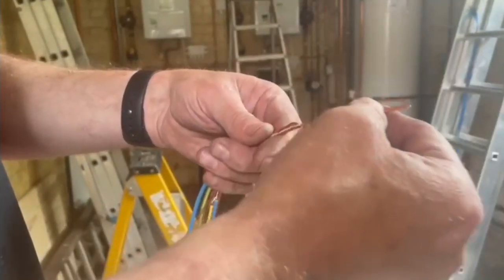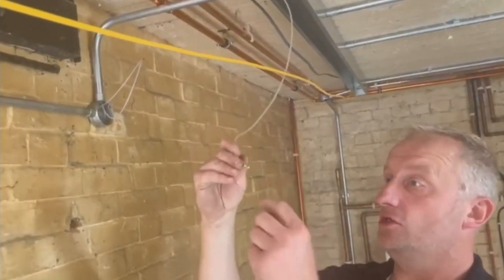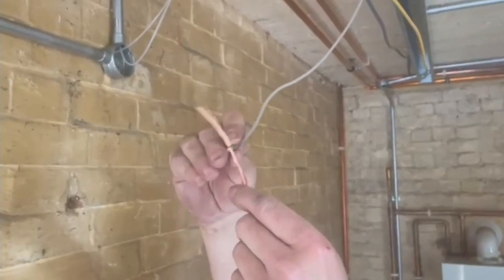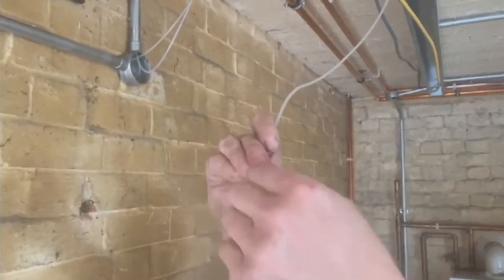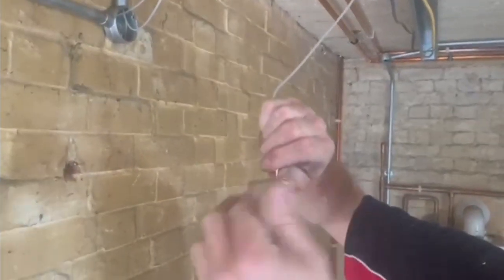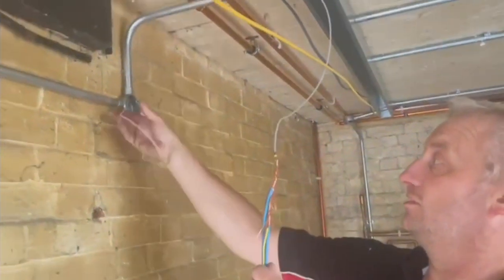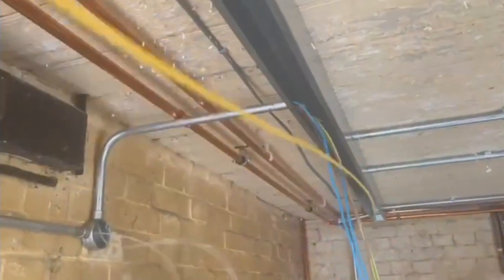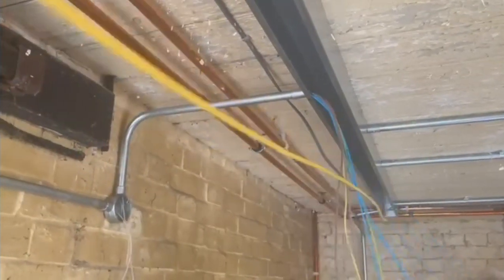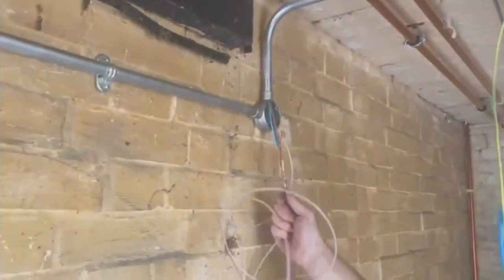So now we're going to take this bit and loop it through our fisheye that we'll bring you back to. You can see we've got a nylon draw tape with our fisheye. So all we're going to do is slide that through our fisheye, and as we did a minute ago, we'll splay that out a little bit, go around two or three times, and then fold it in — so it's a perfectly strong joint. Just to show you that going through there — and that then comes through to there perfectly.